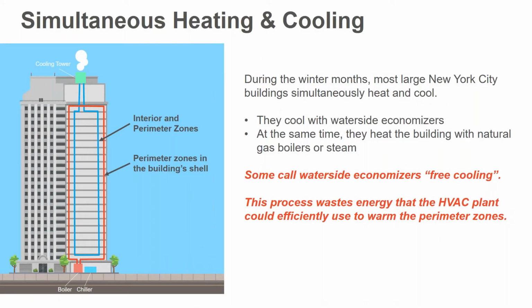So now let's look at heating and cooling buildings with the assumption that you've got heat pumps. So before the heat pumps, when you have simultaneous heating and cooling in buildings in New York, you've got usually a boiler that does the perimeter zones, and you'll have a chiller doing the central zones or the whole building if it's the summertime. But in the fall and winter and spring, we have free cooling, so economizer cycle, right? And so essentially, we call it free cooling, and we are using the cold air outside to cool the cooling tower water, evaporate it, and we cool the space.